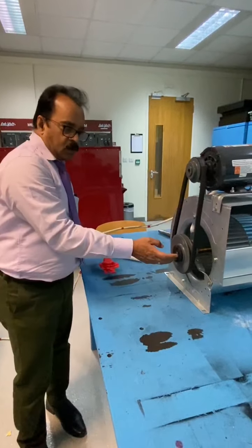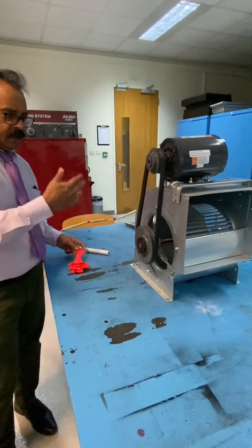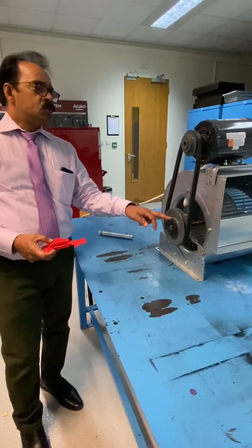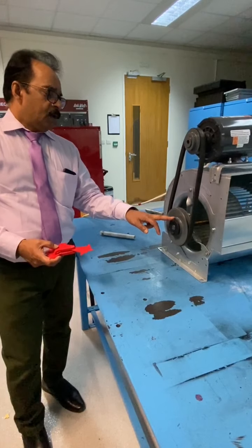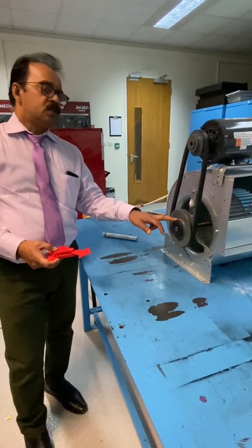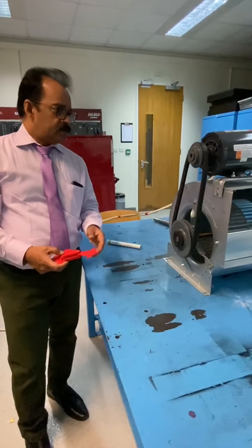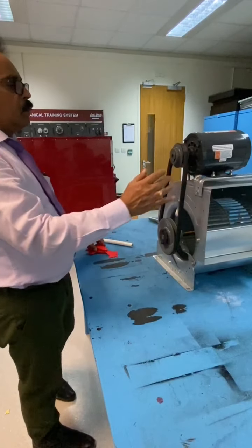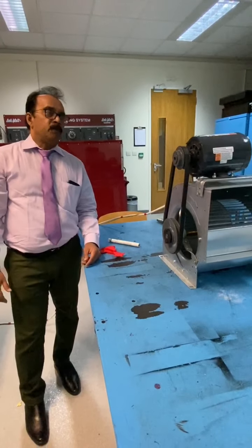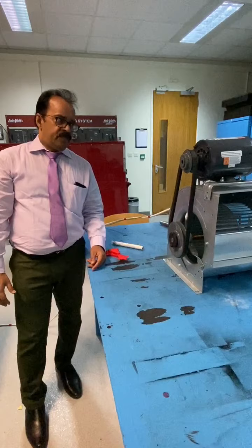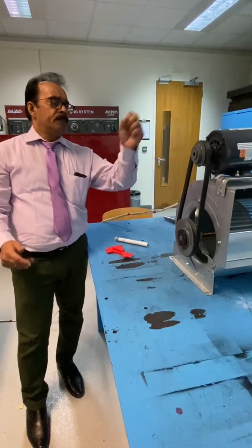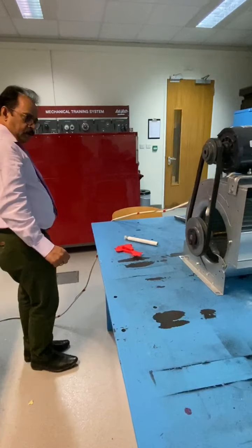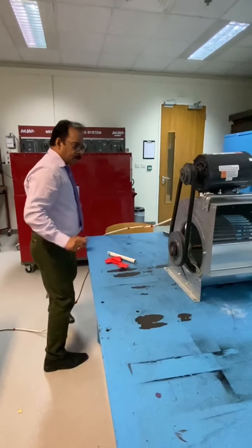Then also the bearing, I told you, if it is running with too much vibration, that means the problem is with the bearing. So you need to replace the bearing, and after replacing, you need to put lubricating grease and things like that. And then the motor also, make sure that it is not running with abnormal noise. If there is abnormal noise, it means there is some problem with the motor. Now we will start the blower.